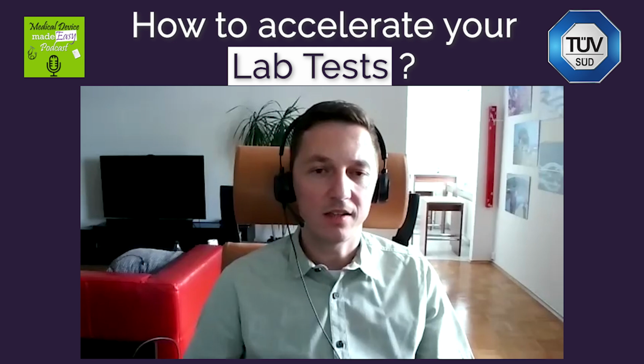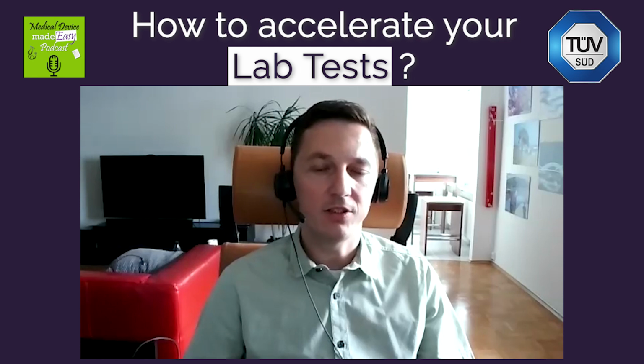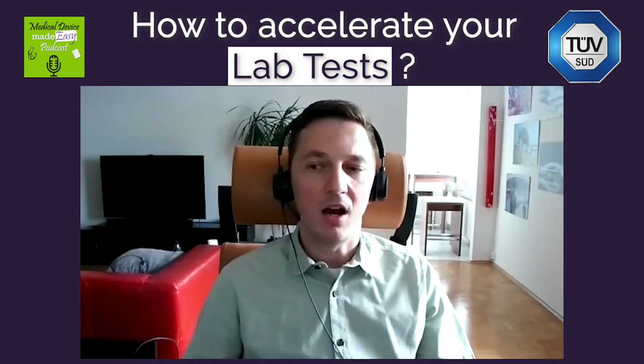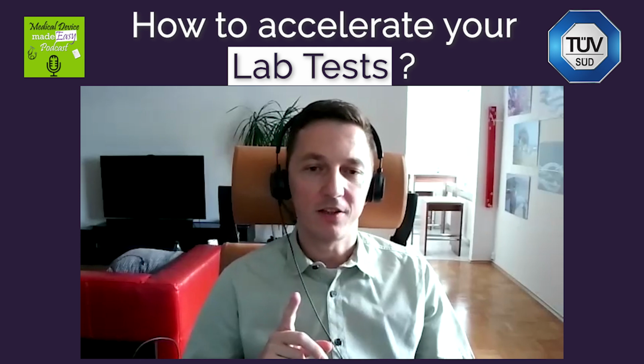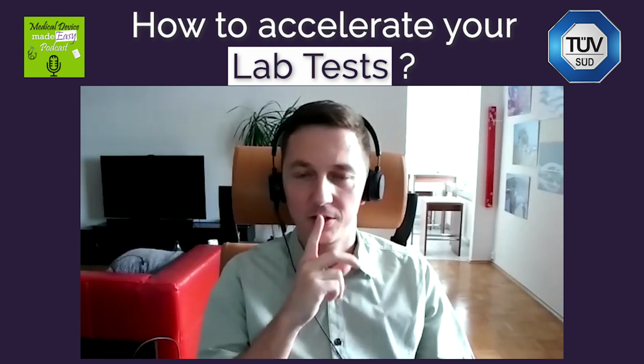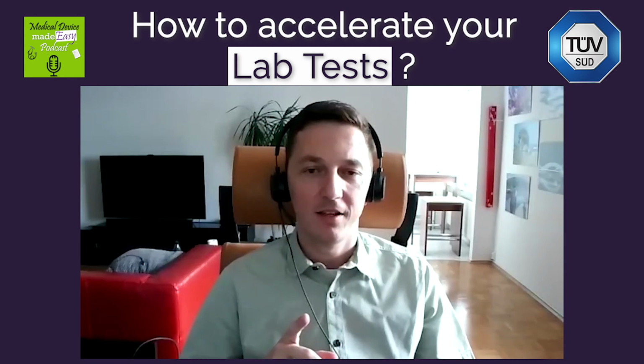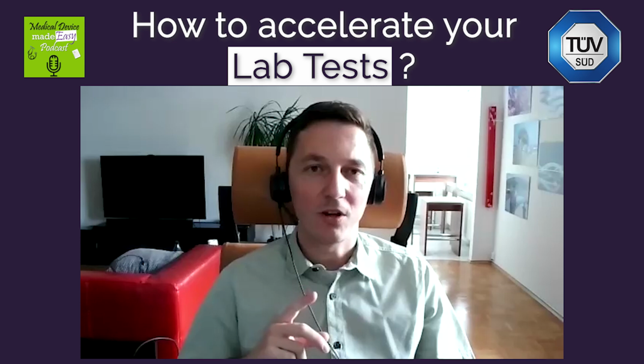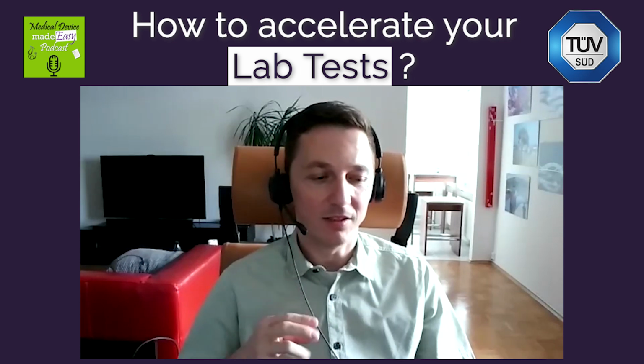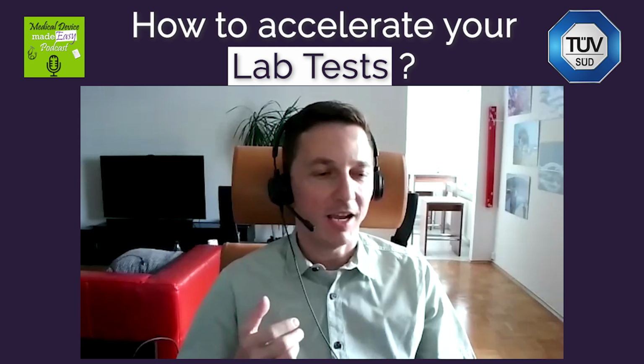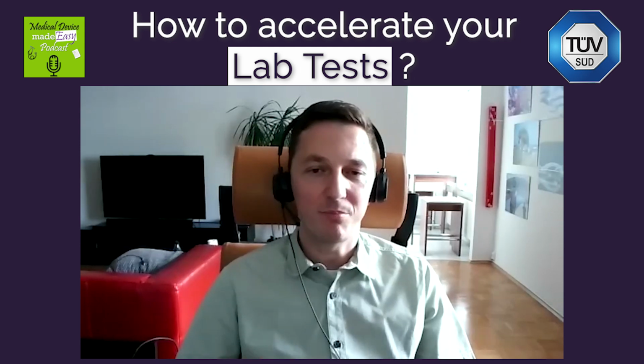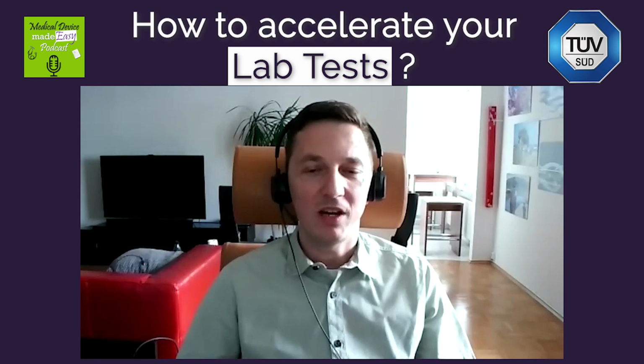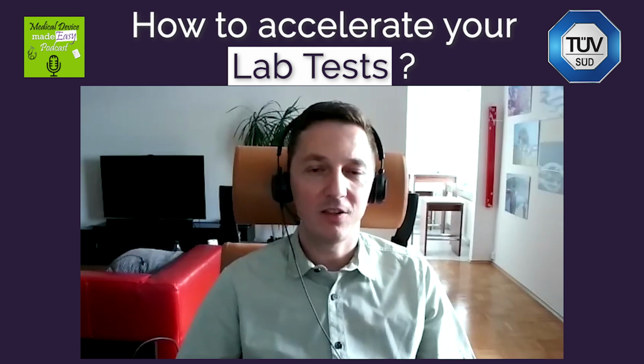And so I had once a customer, and we were not yet at the testing stage, but at the evaluation stage, so the biological evaluation plan, the BEP. And after the first round of evaluation, we wanted to use a second material. Okay. So we did a second loop. We wanted to use a different geometry. Okay. Then we had a third loop. Then we wanted to change the clinical usage, and it will delay the project by weeks and months. So whenever possible, try to get your product final, so that you have a design freeze. Otherwise, you will run into trouble.